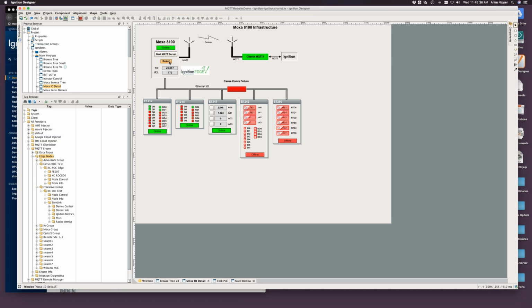I'm going to reset my communication statistics. I'm polling at the edge at 250 milliseconds. But notice how much information we're publishing over the cellular network. None. Because with MQTT, we have state. If we have state, we don't need to keep publishing information that hasn't changed. But as soon as I send a new analog set point, say a new value of 512, that caused the publish to go out, and we immediately got that information updated.